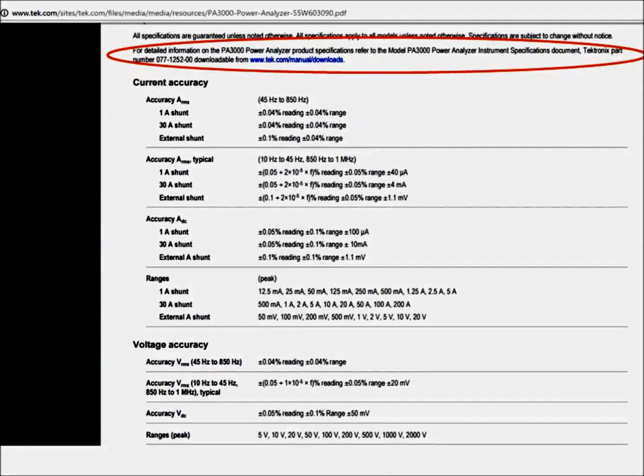Also, I've noticed that there looks like a duplication in the specifications, yet this word typical appears with an extra frequency range from 850 Hz to 1 MHz. And after searching, I found that typical actually means non-warranted. So I understand this to be unproven, else why would this be mentioned? The division of 45 to 850 Hz and then the 10 Hz to 45 Hz and 850 Hz to 1 MHz would say to me that the specifications only apply between the 45 and the 850 Hz frequencies, and this could be a reason why the THD was so sporadic, as it was set to 100 kHz on the current. If the Tektronix though is only proven to 850 Hz, then this is less than 1% of the 1 MHz specification.